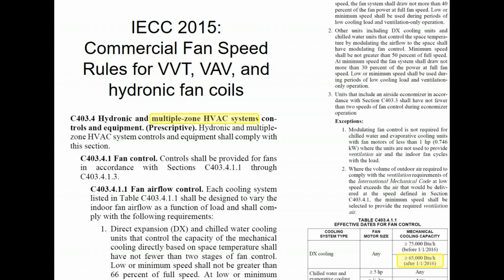So once again, if you have VVT, VAV, Honeywell zoning panels, or any other type of airside zoning system, once you get above 65,000 BTUs on your DX system, you are going to have to include multiple stages of fan operation, at least 2 stages. You can go full variable if you want, that's fine. But you have to have at least 2 stages of fan speed once you have zone dampers. If you don't have DX and you have chilled water systems, then instead of being based on BTUs, it's based on fan horsepower. Once you get to 5 horsepower and up, you'd have to have at least 2 stages of fan speed for chilled water. And if you have evap cooling, which is very rare, then it's a much smaller amount as well.